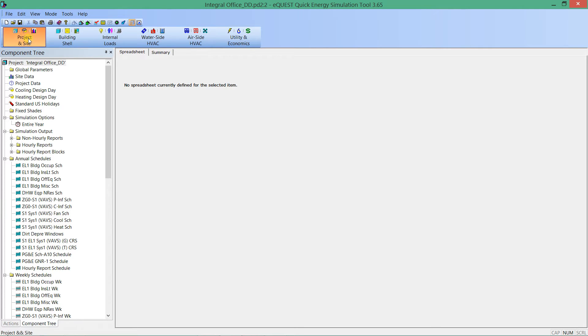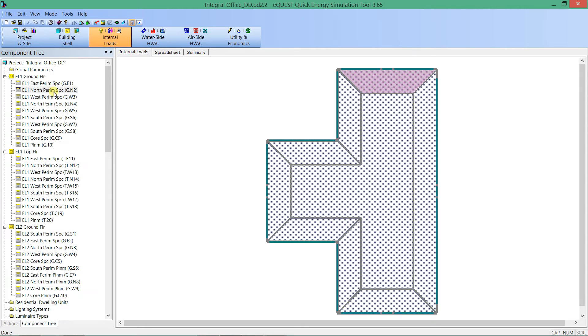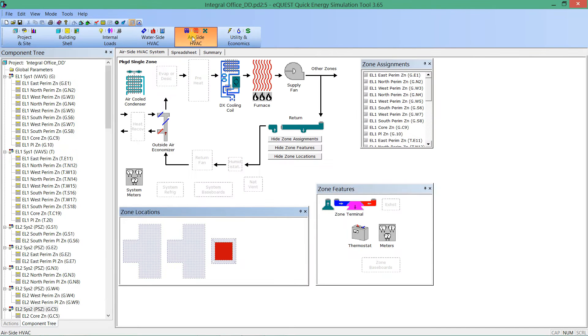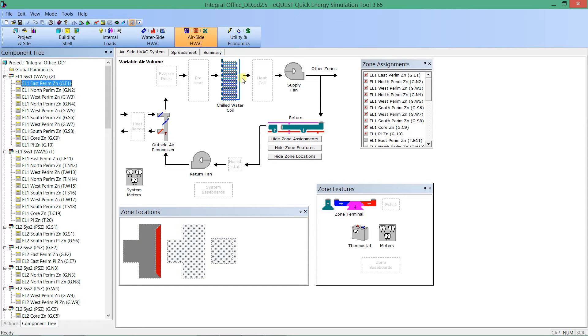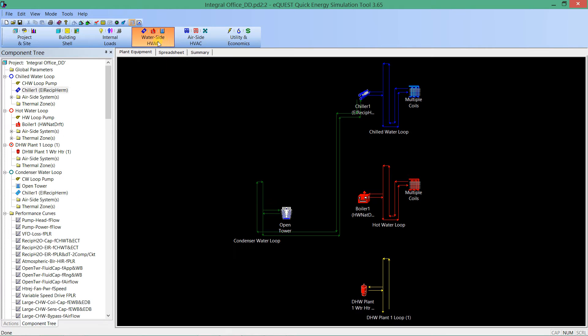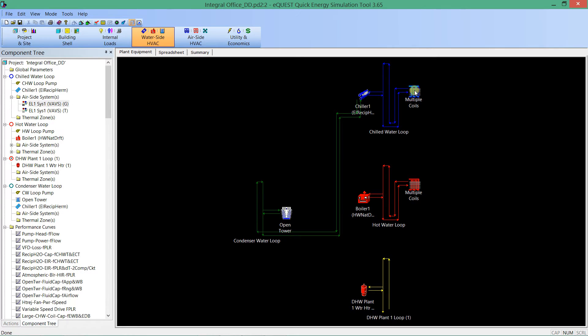We have six tabs at the top: the Project and Sites tab; the Shell — the building where we can manipulate the construction, glass, and shading; the Internal Loads where we can change people, lighting, plugs, infiltration, and daylight sensors. We have two air conditioning tabs. The air side is usually more helpful to think of first, where we define each air conditioning system and the thermal zone set it serves, and then the centralized water side that serves these air systems. So this chilled water coil is attached to this chilled water loop, and clicking the coil shows that it lives inside this air-based system.